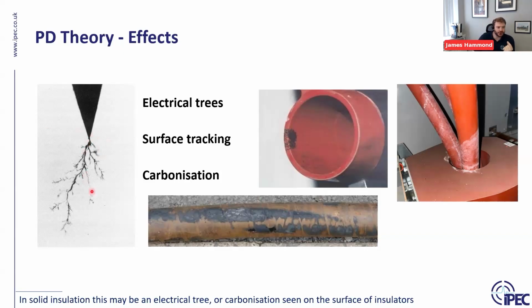What it is, small electrical trees, growing very small amounts, less than millimeters each pulse, until eventually that insulator is completely non-insulating. You can also get things like surface tracking and carbonization, so you can see visible damage. Some of you in switchgear may have seen this. And if you've been into a switch room, I guarantee everyone's seen this white powder, this nitric acid deposit. This is actually a symptom of partial discharge.